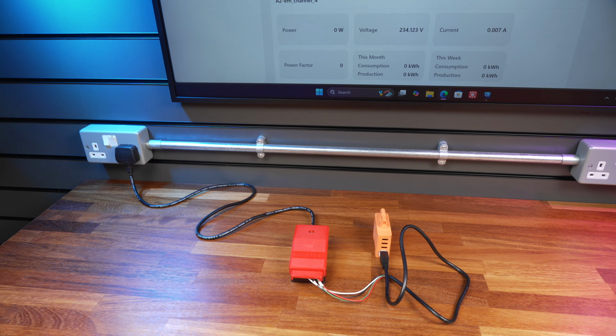And then in terms of examples of power factor, I didn't really go into that previously. Something that would have a power factor of 1, so has no reactive power, would be something that's fully resistive, like a heating element, an incandescent light bulb, something like that. When we're talking about devices that have a lower power factor, that have some reactive component, we're talking about things that have either big capacitors in them, things like motors, things like switch mode power supplies. So generally a lot of stuff you'll have in a modern home, LED light bulbs, compressors and refrigeration, microwave ovens, those kinds of things will often have a power factor of less than 1, which means that the voltage times the current is not the same as the power in watts.